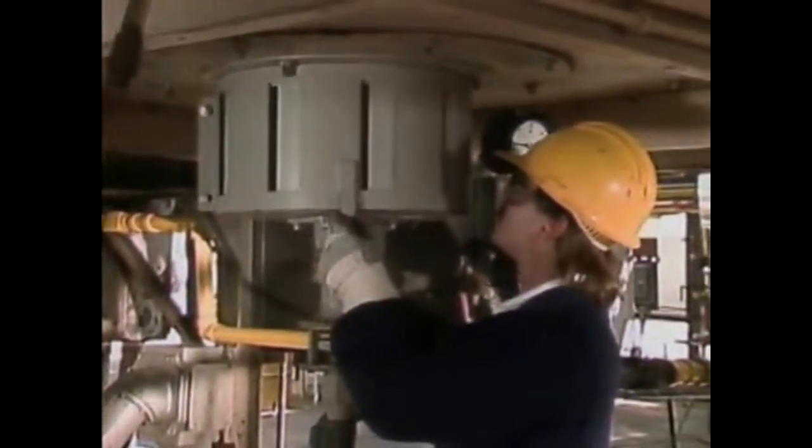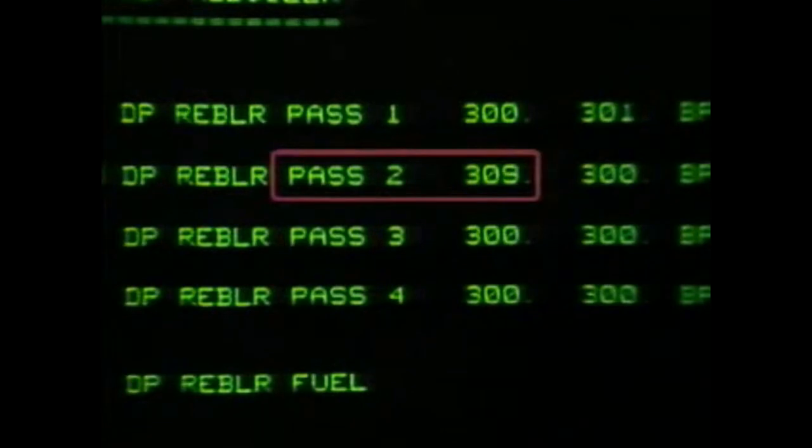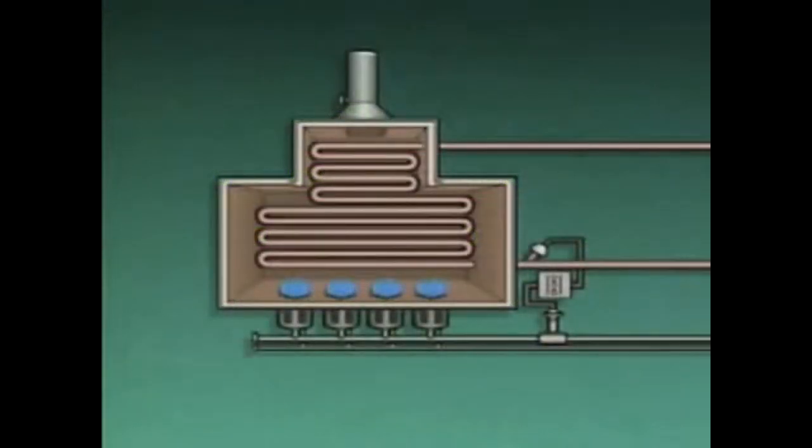If there's impingement, the fix may be as simple as adjusting airflow to the burner to shorten the flame. If reduced process fluid flow causes a hot spot, increasing the flow rate through the affected tube often works. If there's more fluid moving through the tube, it will carry away more heat. Another way to handle a hot spot is to reduce the firing at that area in the furnace. If the burner closest to the hot spot is turned off, you'll direct less heat toward the problem tube.